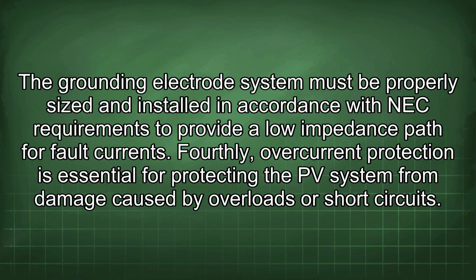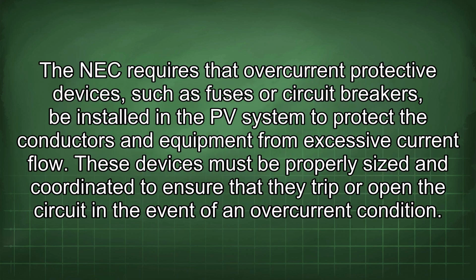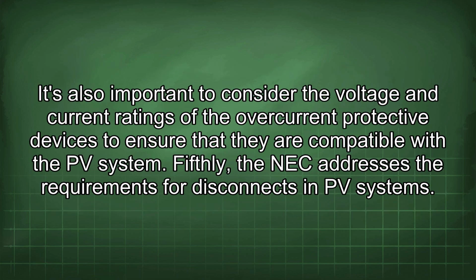path for fault currents. Fourthly, overcurrent protection is essential for protecting the PV system from damage caused by overloads or short circuits. The NEC requires that overcurrent protective devices, such as fuses or circuit breakers, be installed in the PV system to protect the conductors and equipment from excessive current flow. These devices must be properly sized and coordinated to ensure that they trip or open the circuit in the event of an overcurrent condition. It's also important to consider the voltage and current ratings of the overcurrent protective devices to ensure that they are compatible with the PV system.